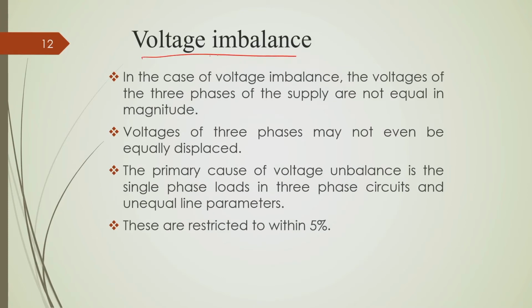Similarly, voltage imbalance is another important type of voltage quality problem. It occurs when the individual phase supply voltages are not equal in magnitude and not equally spaced from each other. These are the two reasons. As we know, when we have a 3 phase supply voltage and it is balanced, the individual phase voltage magnitudes are the same, and they are exactly displaced by 120 degrees from each other. If that condition is not satisfied, we call it a case of voltage imbalance or voltage unbalance. And we will try to quantify this voltage unbalance, and restrict it to a given value.